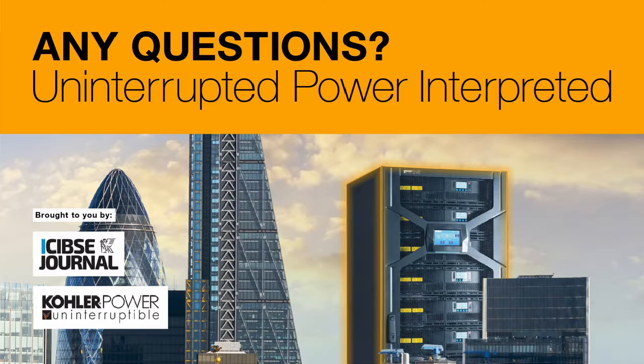Okay. Definitely, yeah. And just to follow on from Vidya there, is there any risk of these lead acid batteries catching fire if a temperature does rise too high in the space? Yeah, there is a small risk. If they're being overcharged, especially, so the UPS should be equipped with some form of temperature compensation. When the battery is warmer, we should reduce the charge voltage. It won't stop the battery getting damaged in the long term, but we can prevent to some extent the risk of thermal runaway. But if you're not treating the battery right, it can be a problem. Okay, thank you for that.